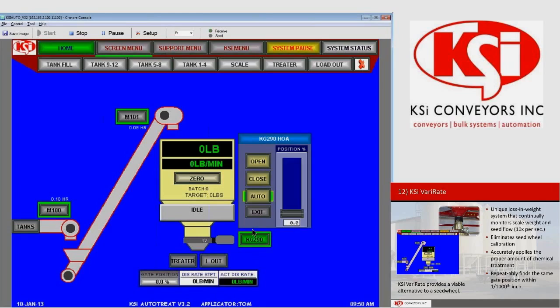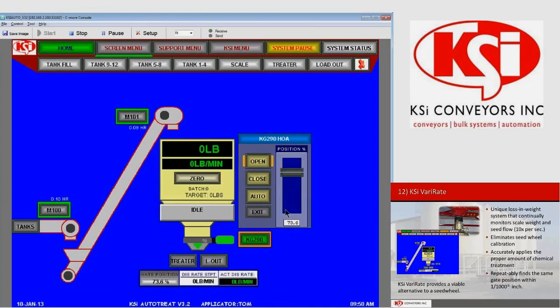If we click on KG 290, it opens up the HOA — the Hand-Off-Auto control for that gate. We have a slider bar on the right that lets us manually control how far open we want this gate to be. As we move the slider bar we can see the position changing both here and in the position field — for example, setting it to 75% open. However, this position percentage is automatically determined by the system while treating seeds, so we want this to be set to auto.